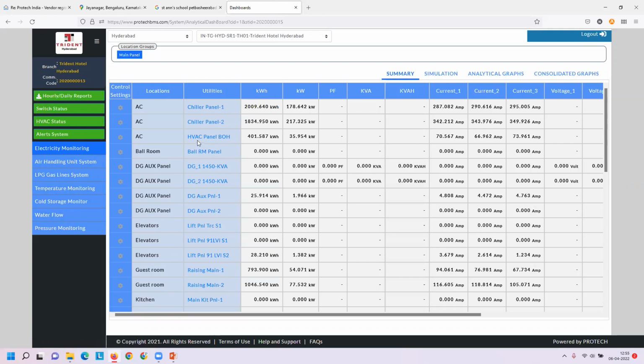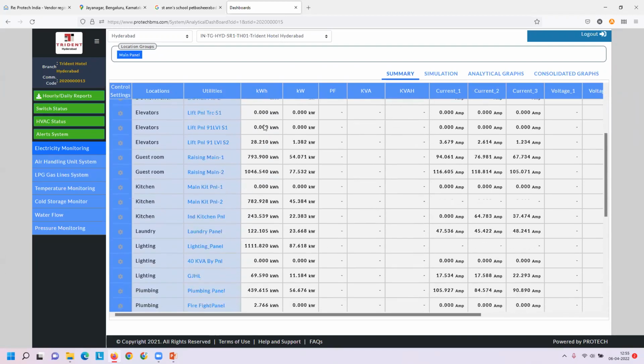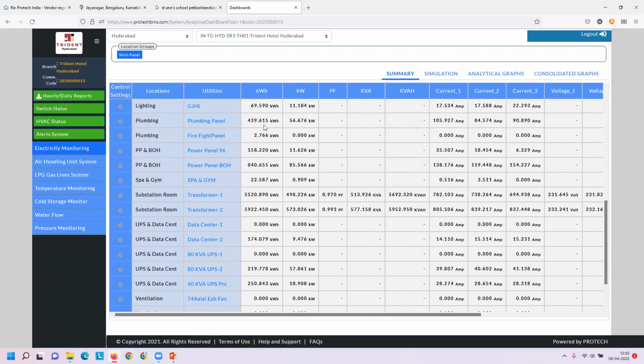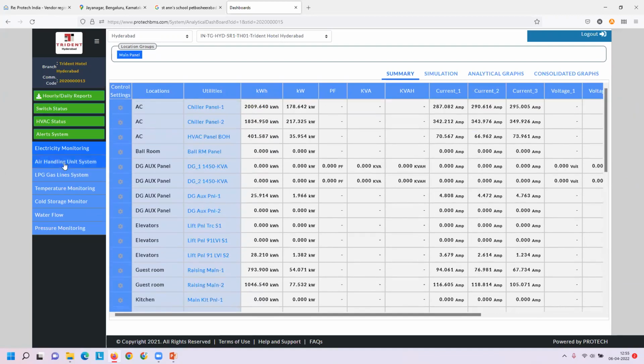So here in energy meter mapping, they have 4 main meters, 2 for incoming transformers and 2 for DG. Apart from that, we have deployed some 30-odd sub meters, which now cover 99% of the entire hotel. The data shown here is the live consumption data of today. So you can see they can have the data. Then let me take you to the air handling part.